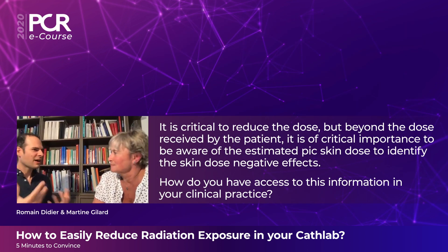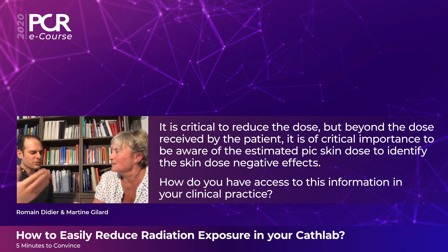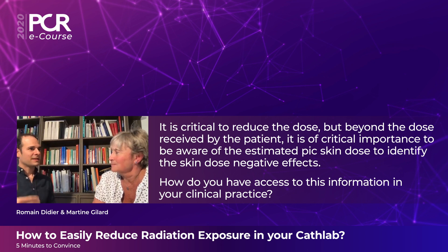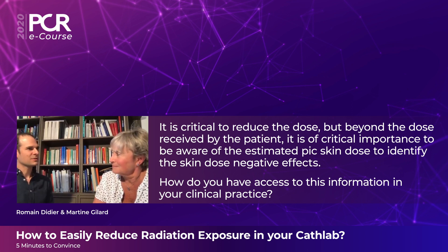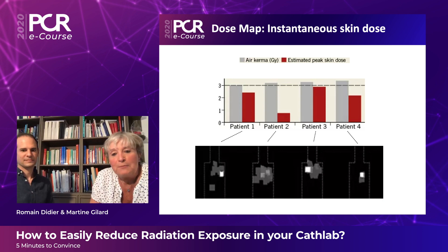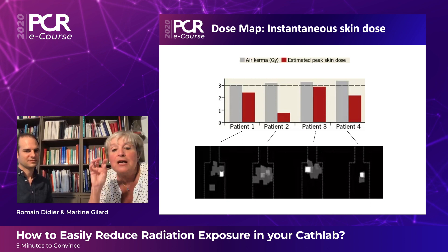We have discussed how to reduce the dose during the procedure. We usually report the dose area product, but as we know, it doesn't reflect the skin dose of the patient. So in your daily practice, how do you assess the skin dose received by your patient? We have the dose map. The dose map is a feature used to calculate, display, and record an estimated local accumulated dose during the procedure.